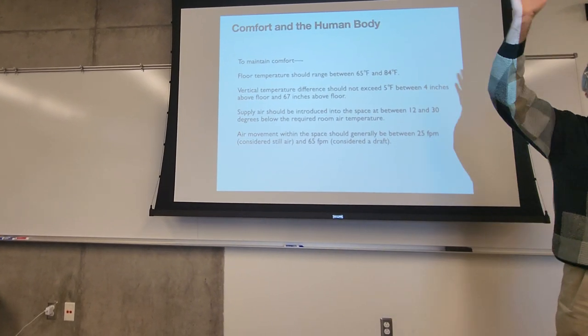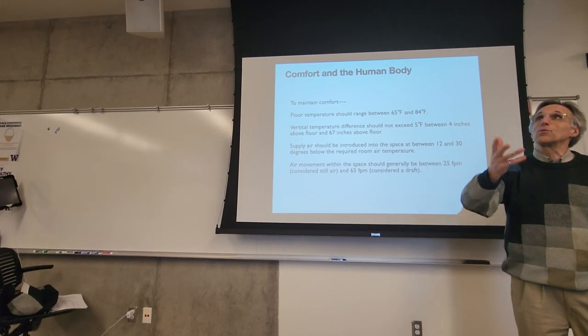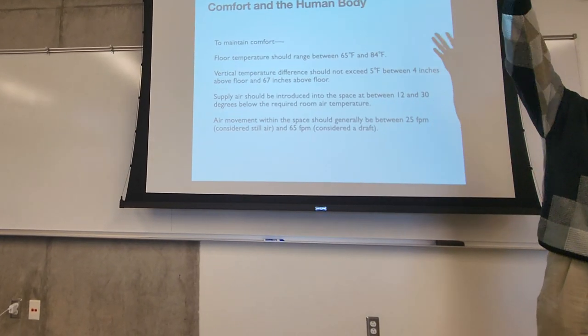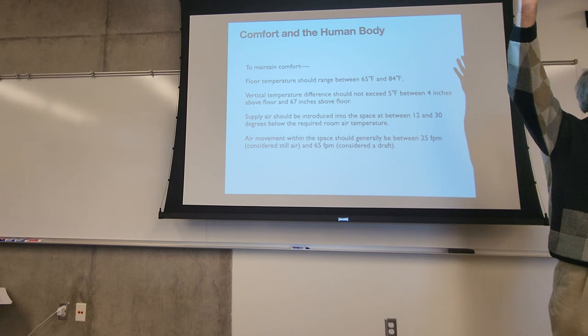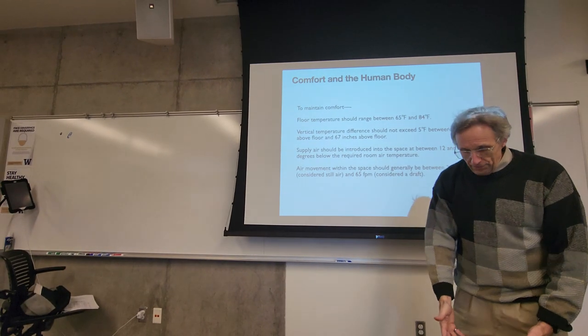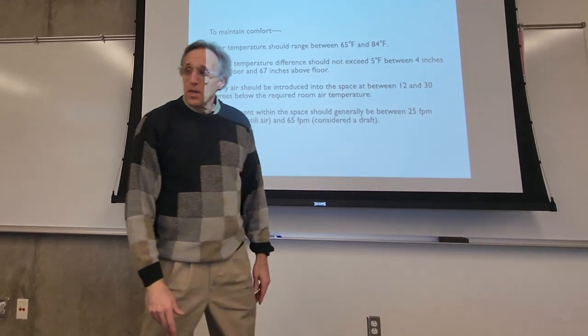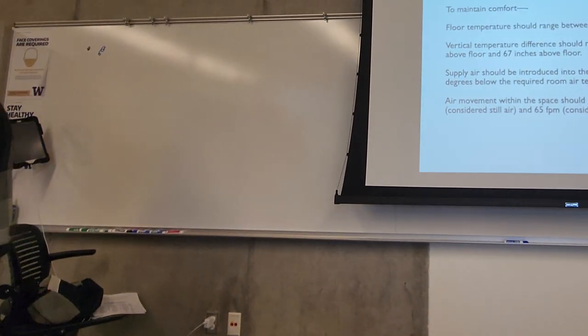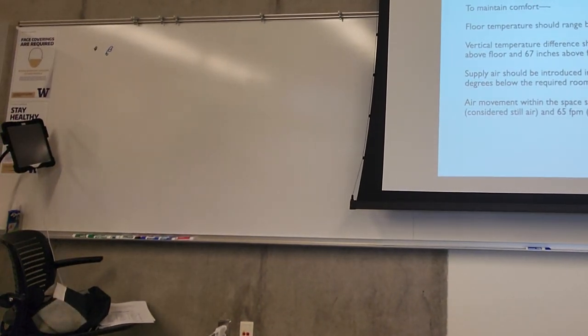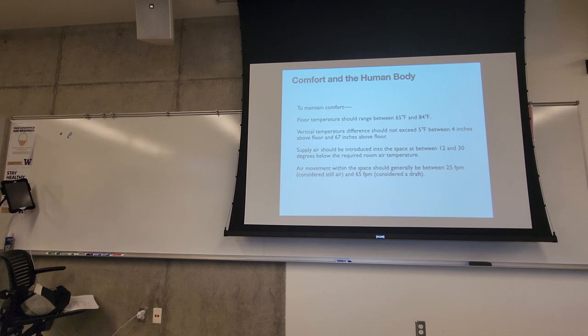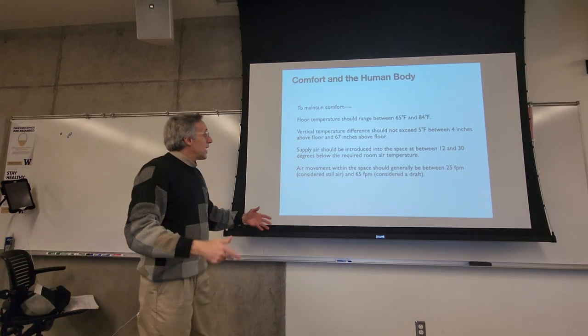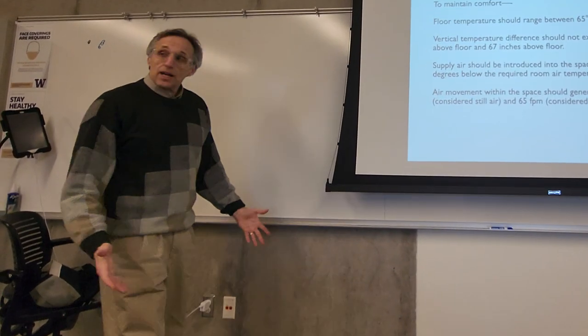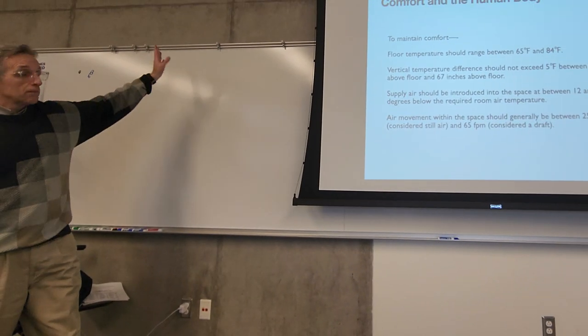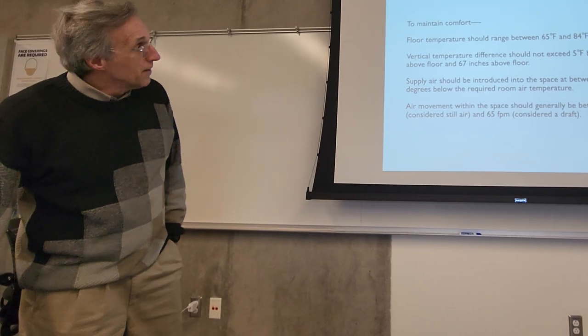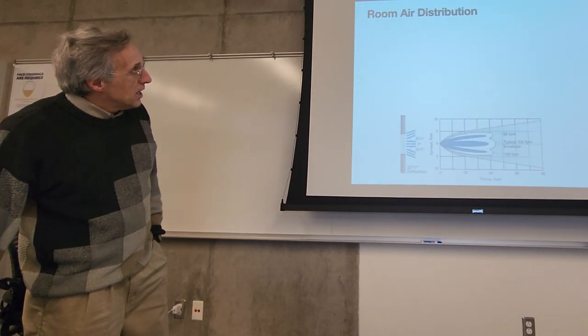Sometimes the architect doesn't give us space down here, or for whatever reason, or maybe it's a retrofit, and we have heating and cooling coming out. Like in my home, my vents are in the floor, my registers, and that's great for heat. It's designed for heating, but it's not so great for cooling. When the cold air comes out of the floor, it doesn't get up high. Stratification, it's warm. I feel that, and it bugs me, but there's nothing I can do about it, because I'm not gonna go drilling, putting in new ductwork and registers and adding a whole new set of ducting.